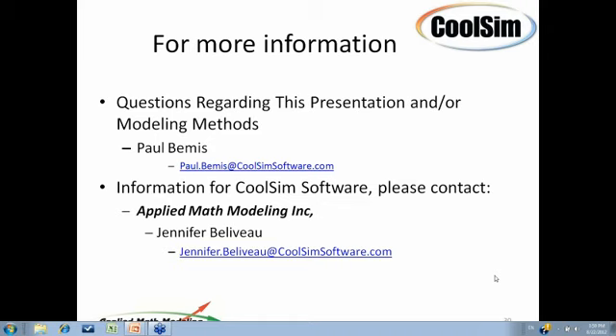CoolSim does allow you to model more granular than that. In our 3.2 version, we allow you to put equipment into the racks and model heat loads down to the 1U level and put the loads anywhere you want in the vertical direction. So in this particular model, I did it at the level of average watts per rack, which is uniform, but it doesn't have to be that way. But that's appropriate if the gaps are blanked, in other words, if any slots that aren't filled with equipment are blanked. I think that's a very appropriate approach to take. Right. Yes, it is, at least in my experience.